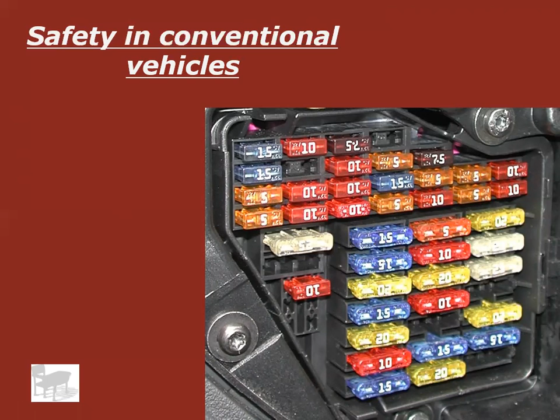So if the fuse blows, that's so it doesn't melt the wire itself and cause damage or start a fire. If you take that 15 out and stick a 25 in that 15 slot because that's all you've got as a spare, and in this fuse block it looks like the only spares are a 10 and a 25, and you stick the 25 in there and the wire continues to have a short, it's going to melt the wire, because the wire is now the weak link, not the fuse. That's not what you want.